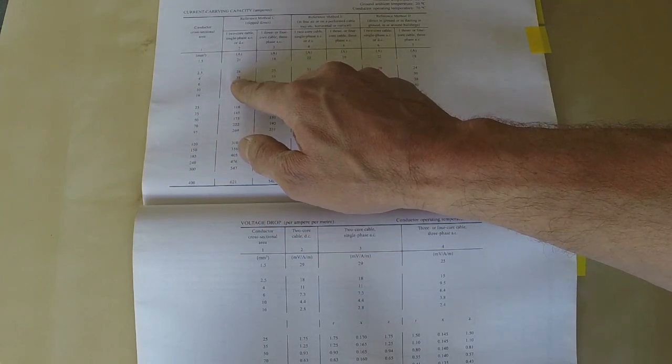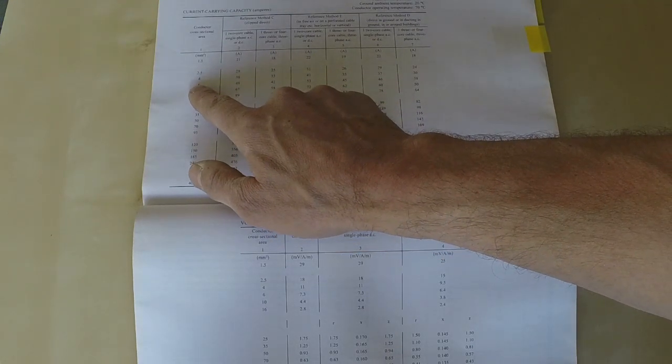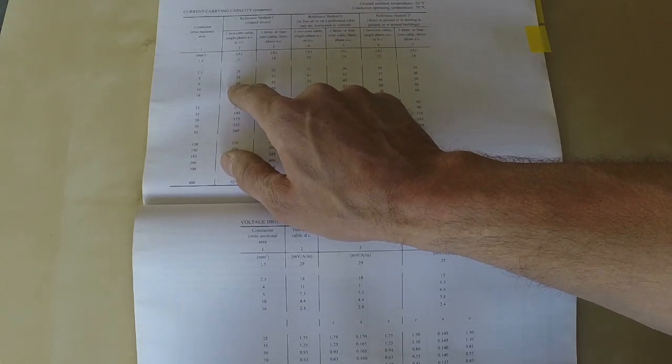Let's just go down until we reach the figure. You can see there, 49 amps, and that's a 6 mil. You basically just go down until you find one that's within the amount you want. So 49 amps, that's plenty, so 6 mil.